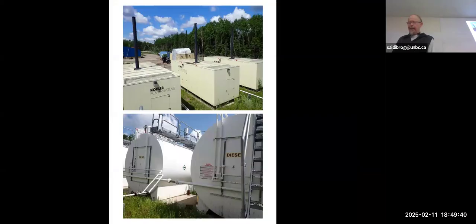When we inspected the building in 2022, the meter on generator number 3, which is this one here, had clocked 10,600 hours since 2016. Now, it hadn't even been turned on except to test it since 2016.